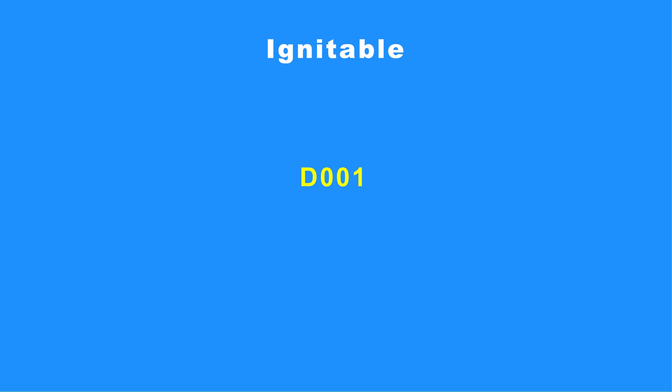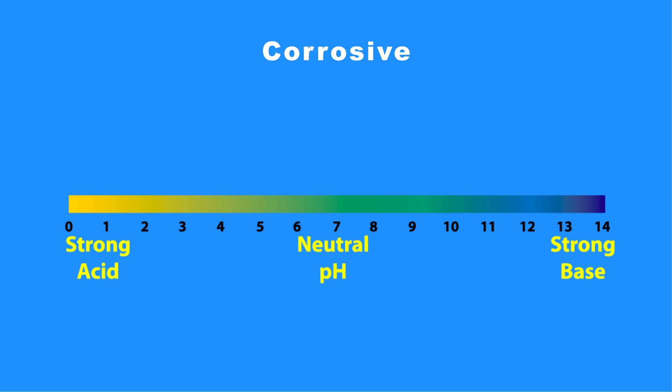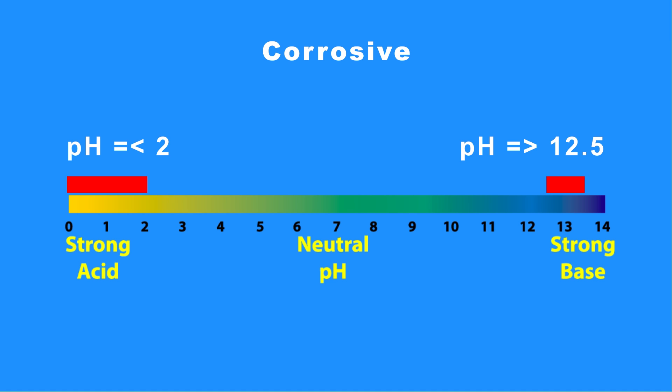EPA has assigned D001 as the waste code for ignitable hazardous waste. Corrosive: Wastes that are hazardous due to the corrosivity characteristic include aqueous waste with a pH of less than 2 and a pH greater than or equal to 12.5, or based on the liquid's ability to corrode steel. EPA assigned D002 as the waste code for this type of waste.